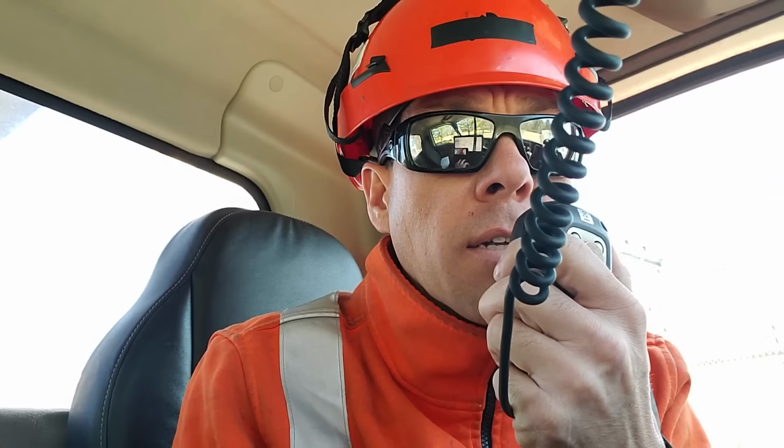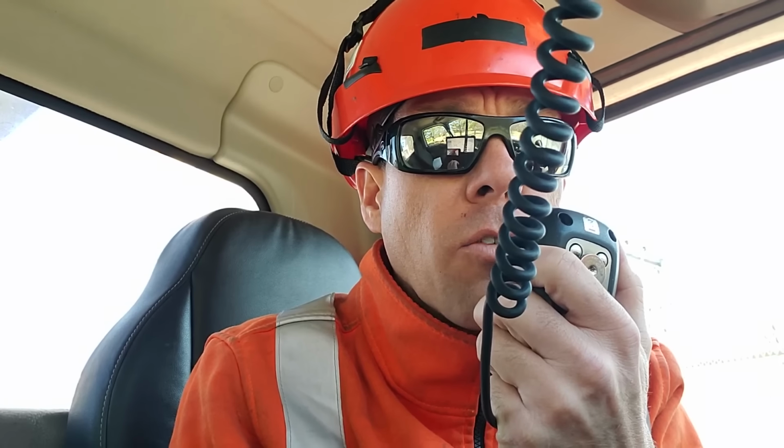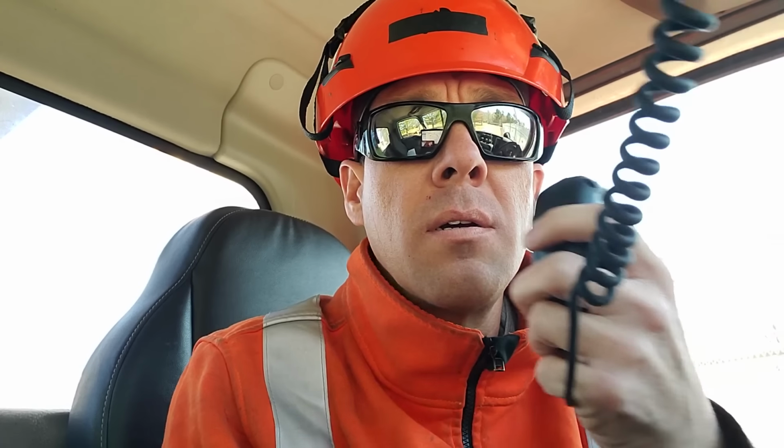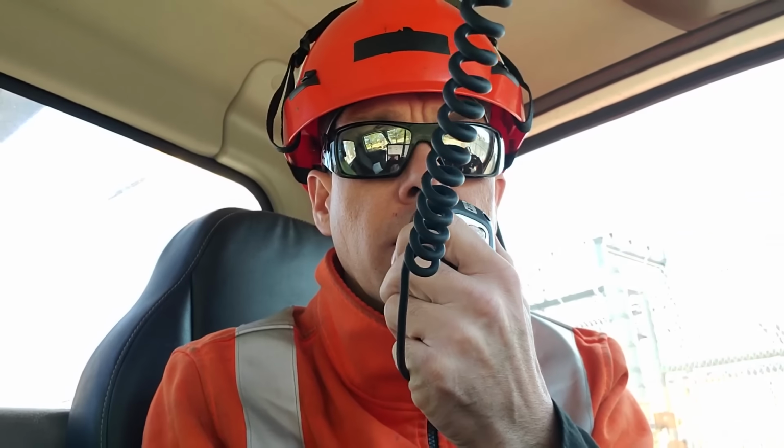Before you say 6518 R003 is open. Yeah, 10-4. I was showing over 5,000 amps fault in all 3 phases there. Oh, is it on all 3? I just see it on the waveforms here on 2, which could be like a phase flap or something, but if you hold on 1 second, I can tell you how far from the sub it is. Hold on. Yeah, thanks.